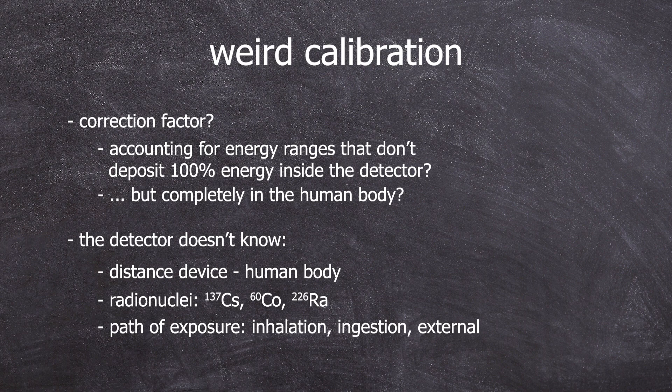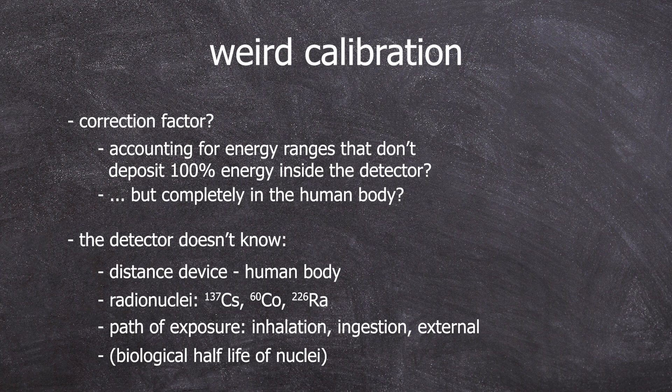Another thing that the devices cannot know is in what form are the radioactive sources? Is it radioactive dust that can be inhaled? If so, how big are the particles? Is it in a form that can be ingested? Or is it just external radiation? A dose rate meter tries to summarize all these factors with a correction factor and yes, it must be calibrated to some radionuclei and all the nuclides are then just approximations. But I don't know which radionuclei they are calibrated for.